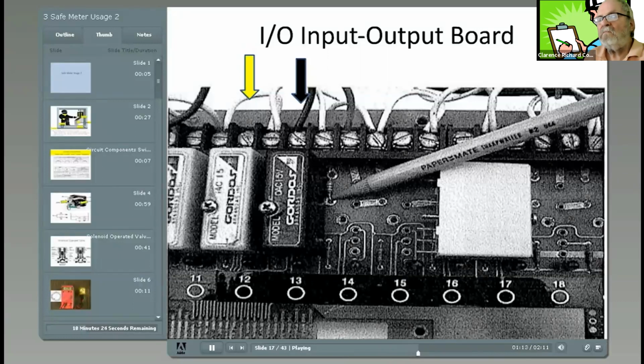If the solenoid valve does not operate, check for 120 volts AC at the terminal. If there is no 120 volts AC, the replaceable fuse or module is bad, and one should be replaced. The pencil is pointing to a fuse, which looks like a resistor. It can be pulled right out.